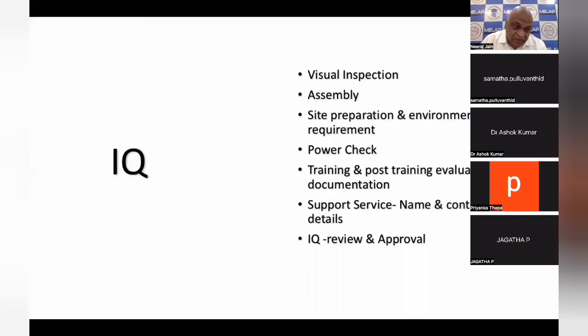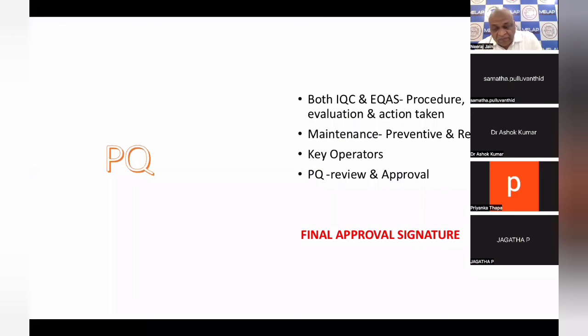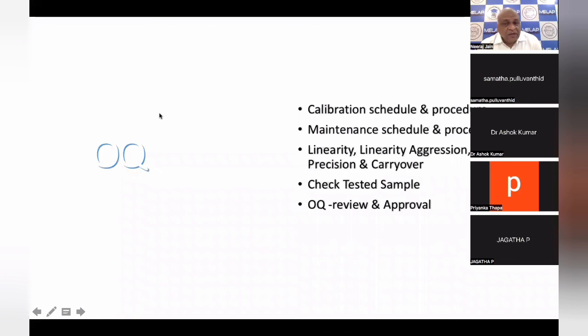But your machine is still not ready for the unknown sample to be tested. Get your machine calibrated with the help of a calibrator. And this calibrator shall have metrological traceability, as we discussed. You shall have a calibration schedule. Maintenance of the machine, as we discussed. Daily maintenance, weekly maintenance, monthly maintenance, once in 3-4 months, company people are coming. And in verification, you are documenting this linearity, regression analysis, precision, carryover on your machine, as we discussed.